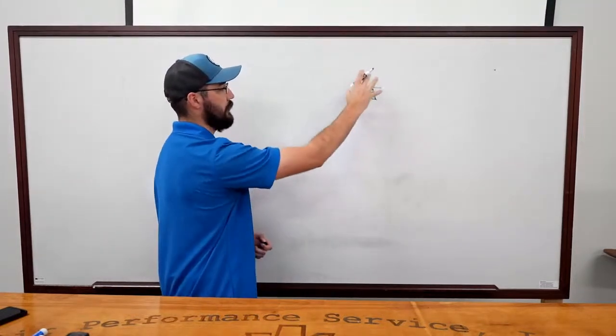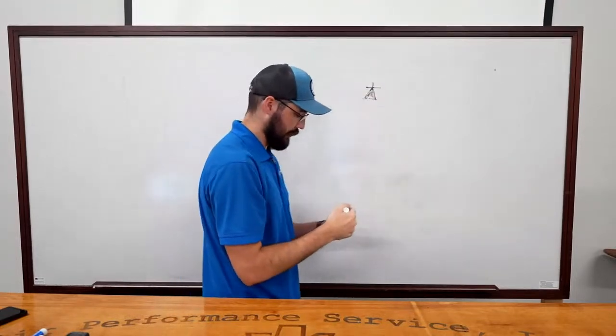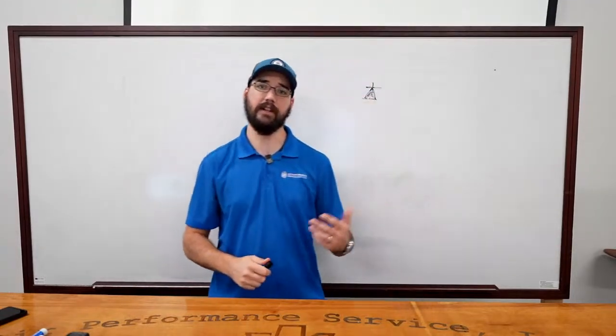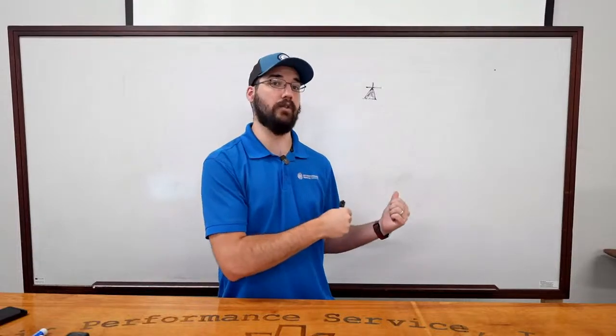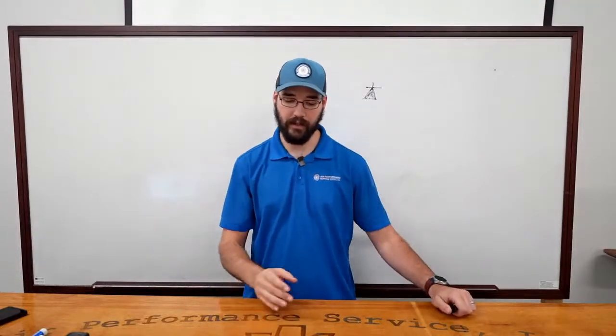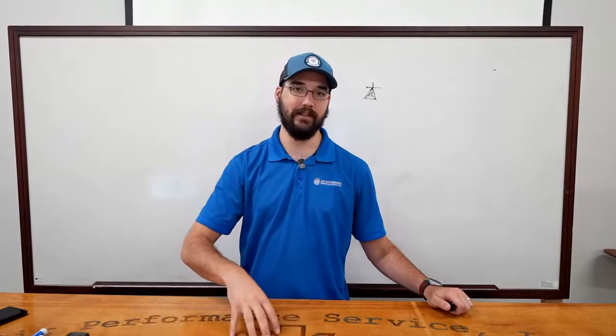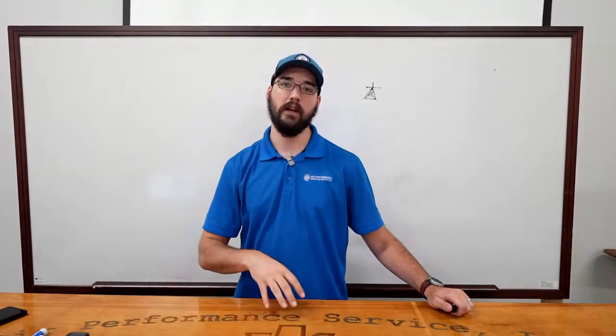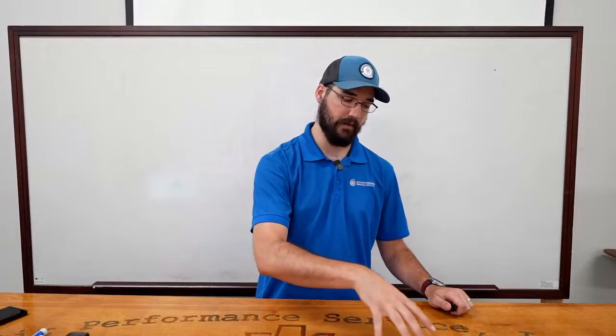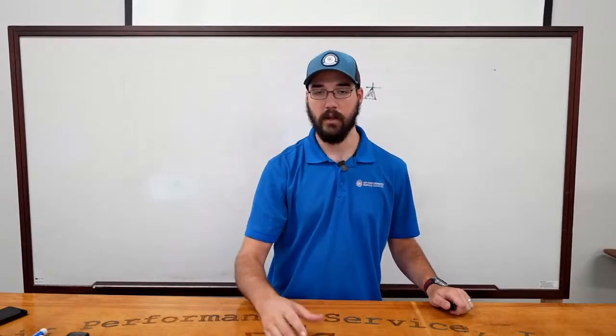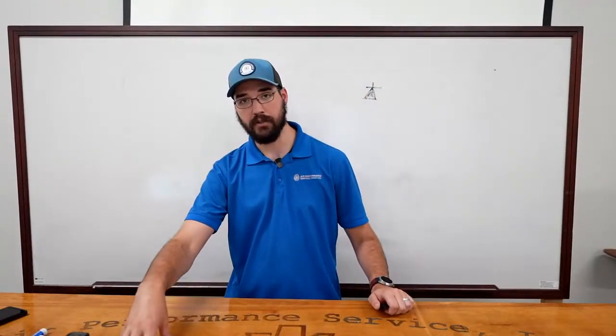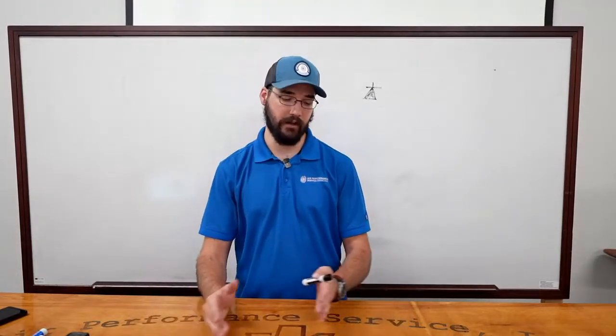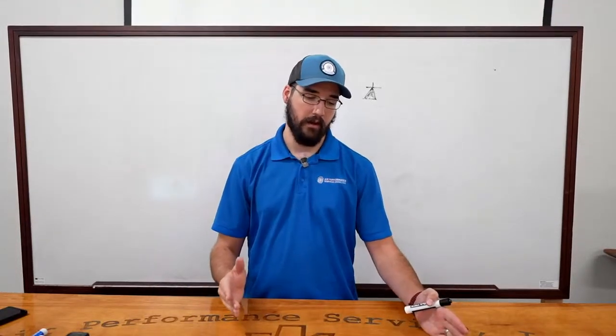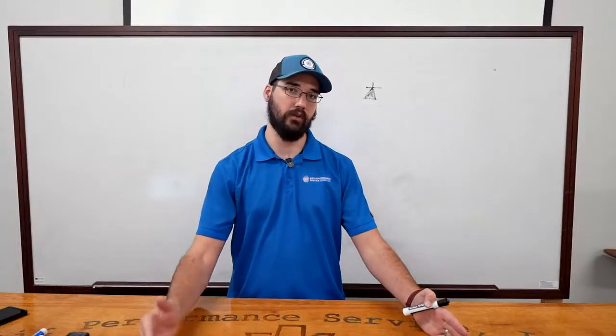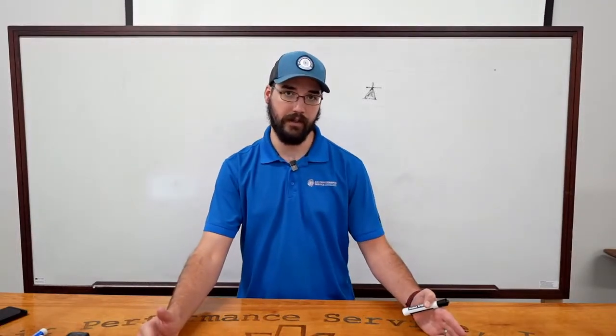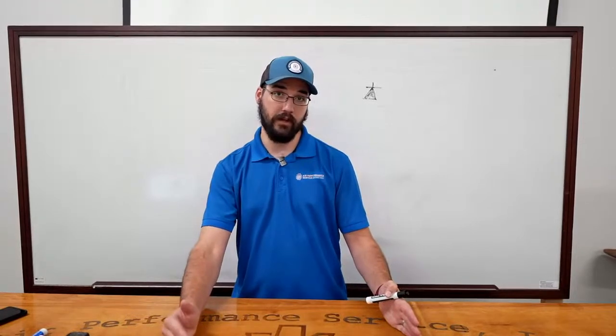And you'll have a symbol in whatever orientation it is. That is an indicator of a diode test. And part of what that's testing is how much DC voltage is allowed to leak through the gates in the inverter, for example. So if we have too much of that voltage, it should be a set range. A lot of times, like 3.5 VDC to say 4 VDC, maybe a specific range that they're looking for.